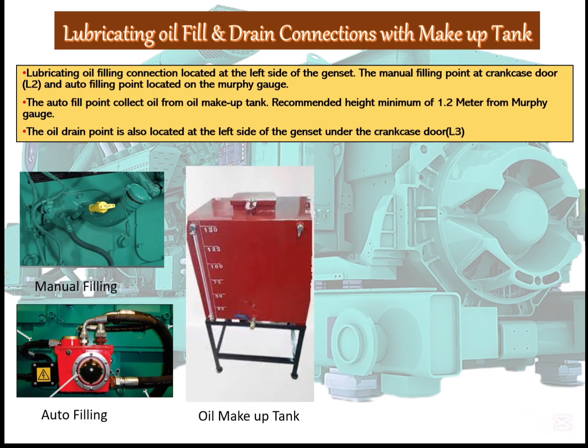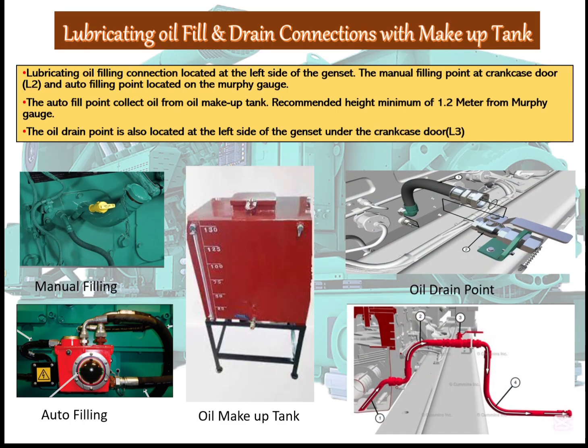This is the auto filling Murphy gauge that is also located on the left bank. So the pipe will connect from the makeup tank. Whenever the engine oil level is lower, the oil will come with gravity, and auto filling will complete the top up. This is the drain point. It is also located on the left bank side. When we want to drain the oil, we need to use an external pump to suck the oil from the sump. So all the oil fill and drain connections, manual and auto, are located on the left side of the engine.